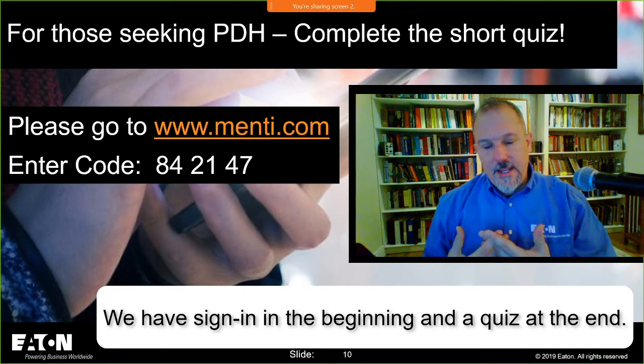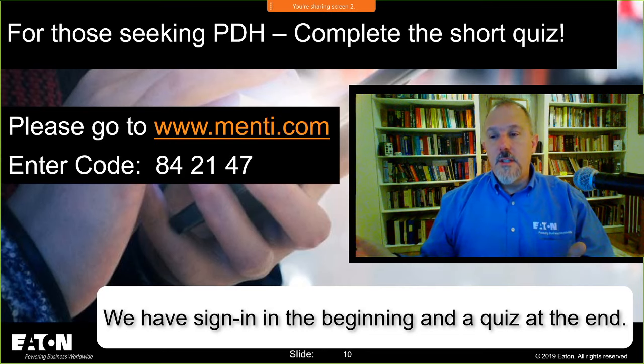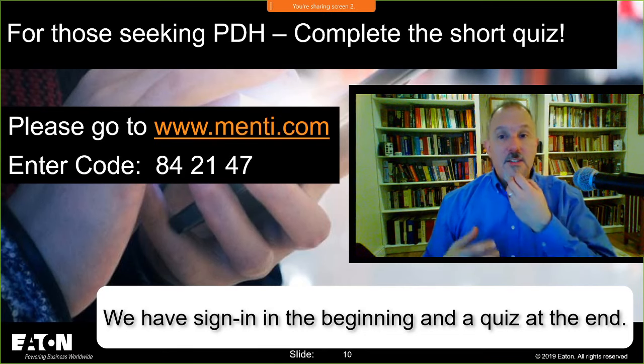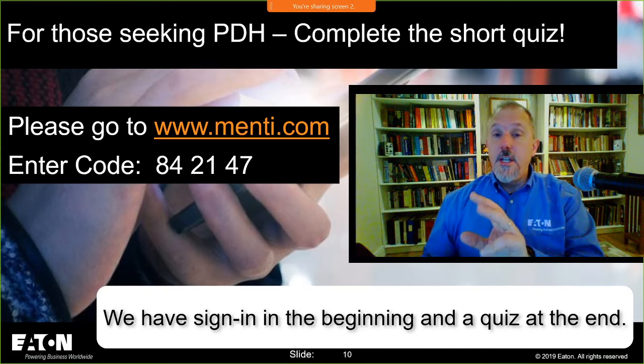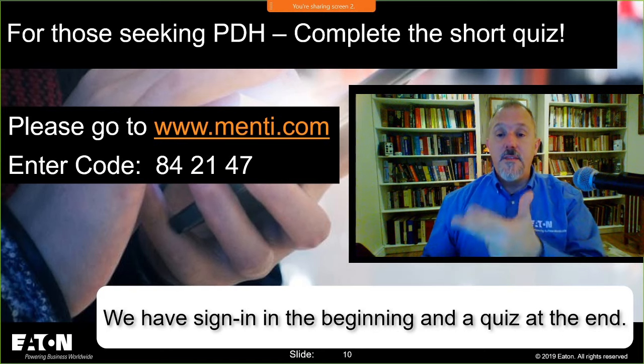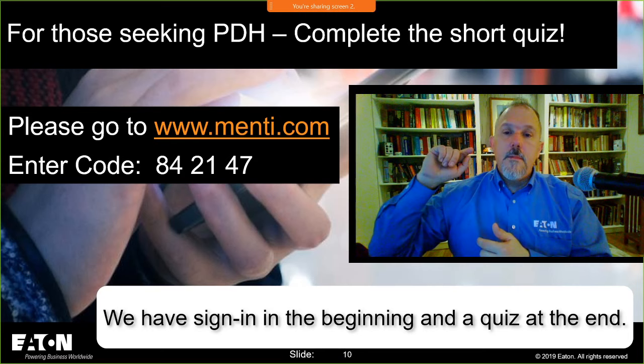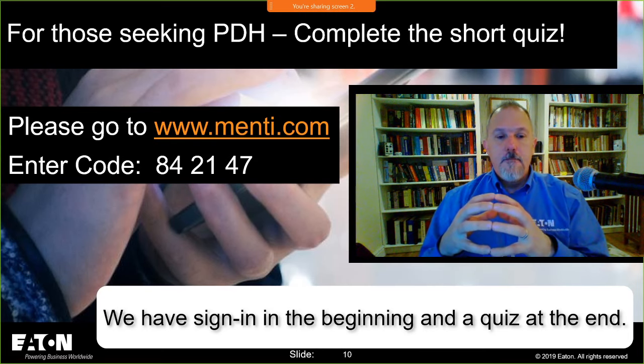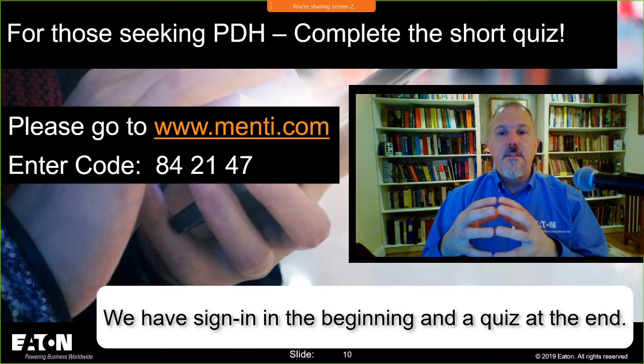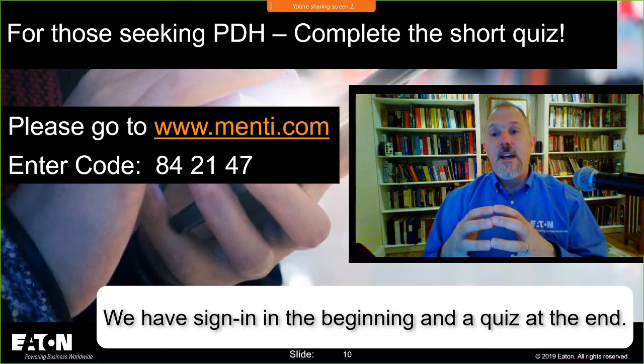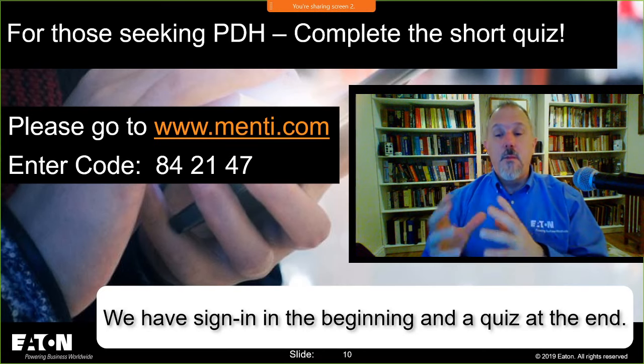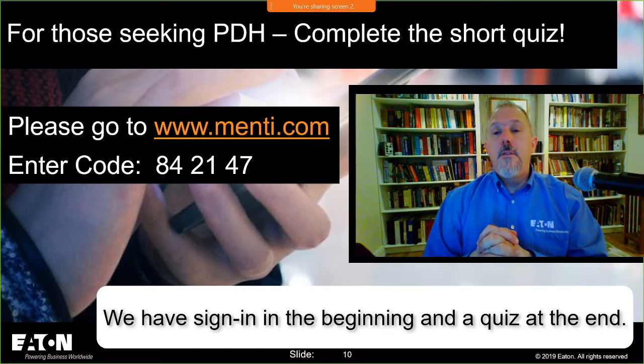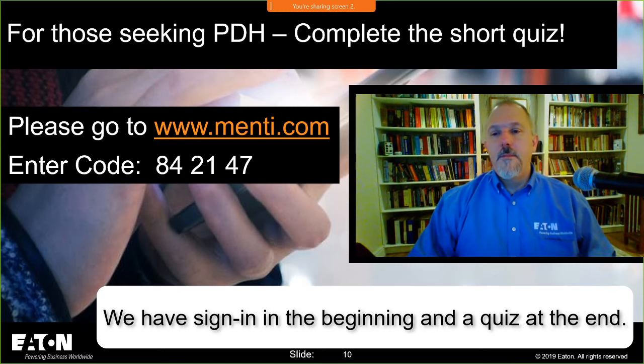The other question I usually get is, what about after the initial install, right? How often should we be testing these things? And that's really a 70B, as in Bob. Remember the trilogy? 70, 70E, and 70B. 70B is on maintenance. 70B is an important thing. So you should be periodically testing your zone selective interlocking. I know that our Eaton products now have an indicator to show that ZSI is active and working and there's integrity there. Not all manufacturers have that. So that's why periodic testing is going to be really important, and a lot of this is secondary current injection testing, so you're not ripping things apart.